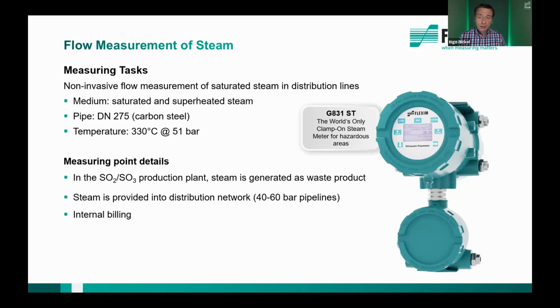Another very important point: steam measurement. Flexim launched two years ago the first clamp-on steam flow meter. This means we are able to measure low temperature steam, but also high temperature steam, without opening the pipe and then introducing any kind of equipment into the system.